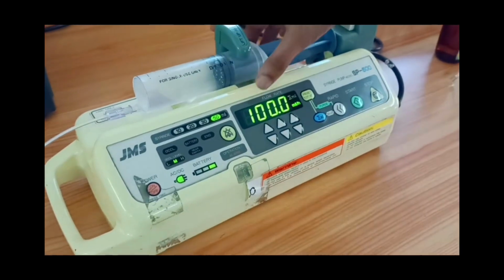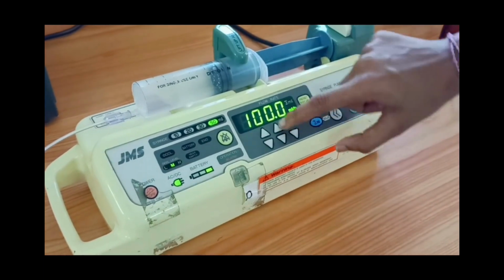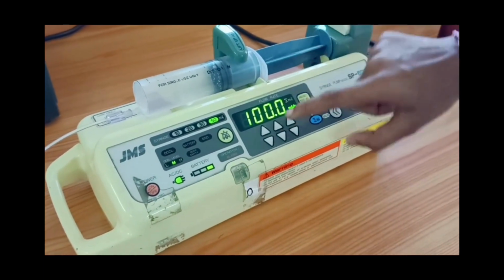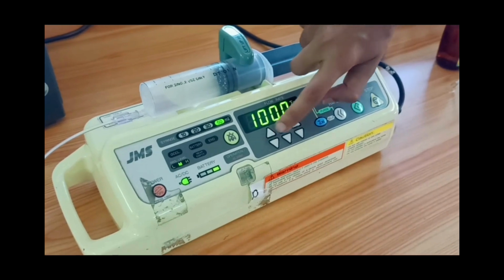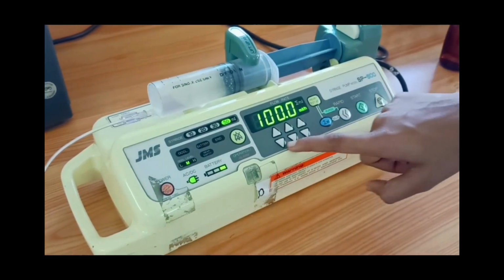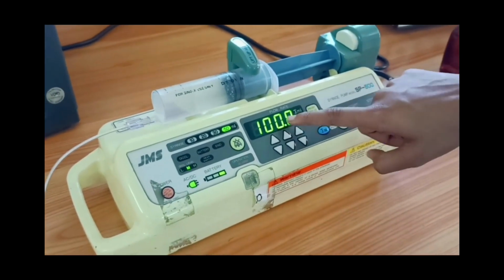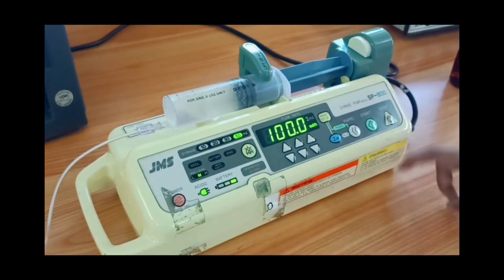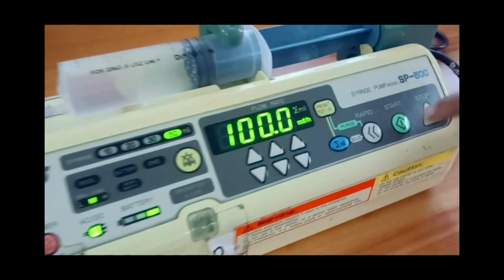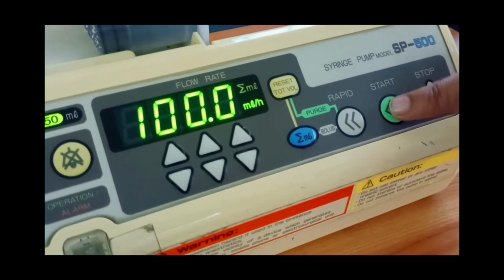Now first I have set the flow rate by using these buttons. The upper ones are to increase the number and the lower ones are to decrease the number. I have set the flow rate to 100 milliliter per hour. Now I am starting the device. Press this button to start the syringe pump.